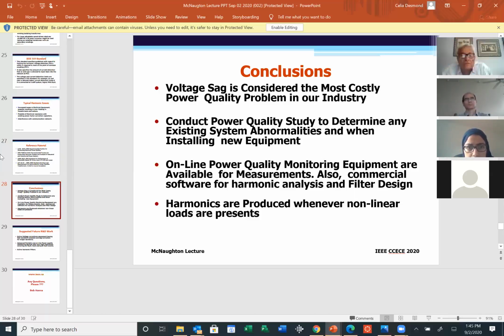Last bullet point: harmonics are produced whenever non-linear loads are present, meaning anytime you convert a waveform from AC to DC, DC to AC, or DC to DC, whatever way, then the input waveform and the output waveform will contain some harmonics to a certain degree, depending on the design. Next slide, please.